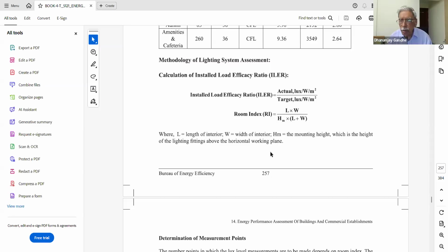That means the actual lux that we obtain from the lighting system, per m square, divided by the lux level that was provided at the design stage. So the term is the target lux level. The ratio of actual lux per watt per m square and target lux per watt per m square is called the installed load efficacy ratio, ILER for short. Lux per watt per m square is the parameter to work out physically and compare with the target given in the design figure.